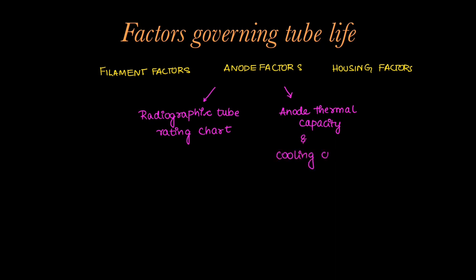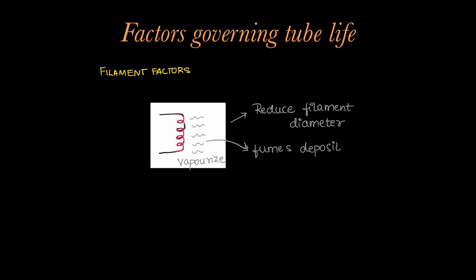Now we will learn what are the factors governing the tube life. There are filament factors related to cathode, anode factors related to anode, and housing factors. The filament in the cathode is made of tungsten. Once heated up, it will emit electrons. Also, the metal vaporizes over time which reduces the filament diameter, and the fumes will deposit onto the glass envelope, reducing its life.